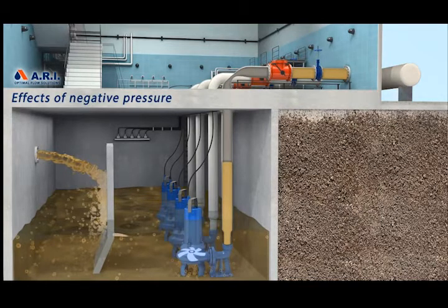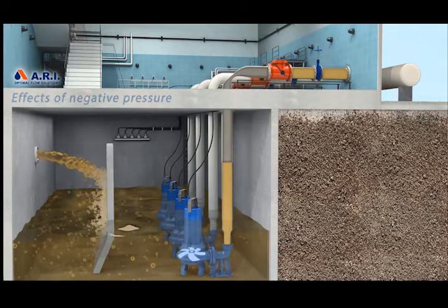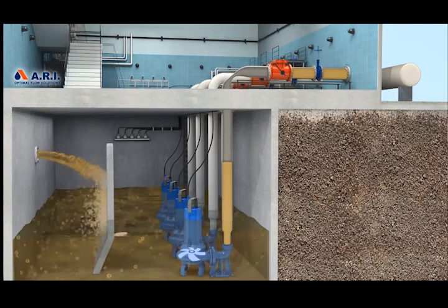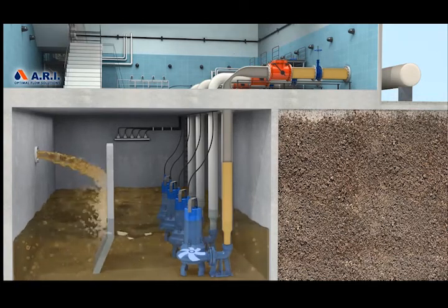In addition, if we don't allow air in, the sewage line itself won't be completely drained down, as we can see here. And if it's maintained for long, this could build up grease, fats, and residue on the undrained water column that could eventually cause some blockage.